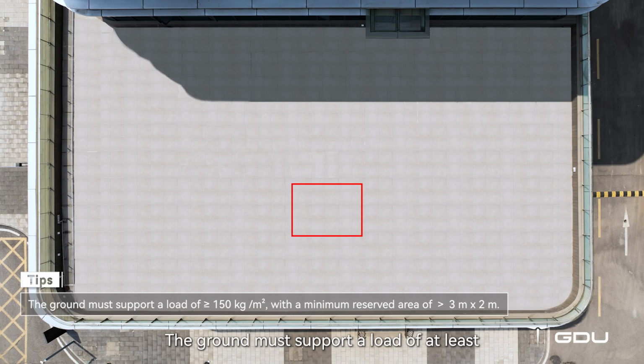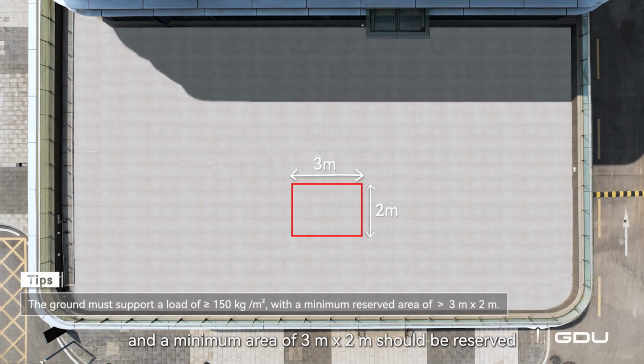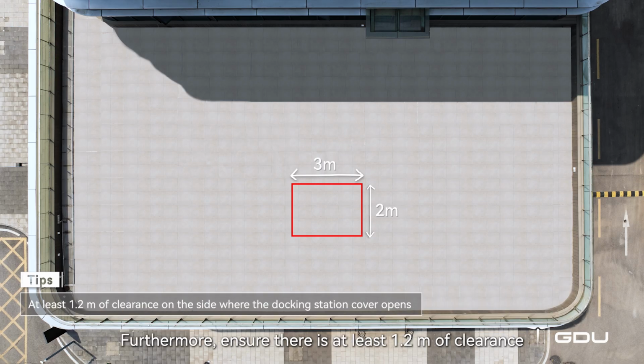The ground must support a load of at least 150 kilograms per square meter, and a minimum area of 3 meters by 2 meters should be reserved. Furthermore, ensure there is at least 1.2 meters of clearance on the side where the docking station cover opens.